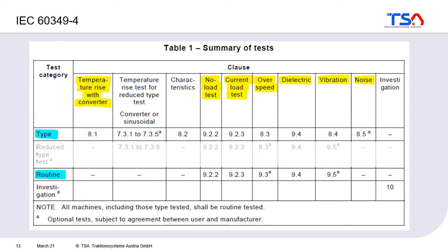The standard specifies which tests should be performed. First is a temperature rise test with a converter. To confirm electromagnetic performance, a no-load test and a current load test are conducted — these are also part of routine tests. To confirm mechanical integrity, an overspeed test is done. Insulation is checked via a dielectric test. Additionally, the machine must be checked for vibration — measuring vibration velocity — and for noise.